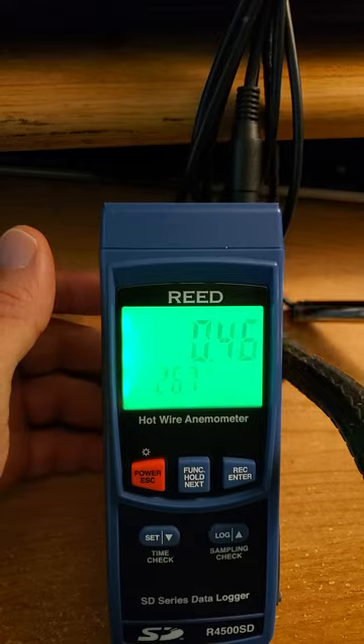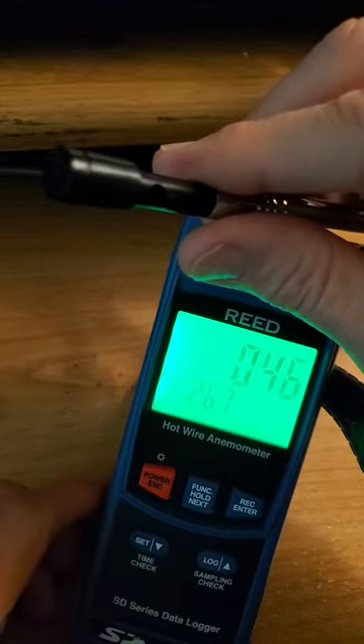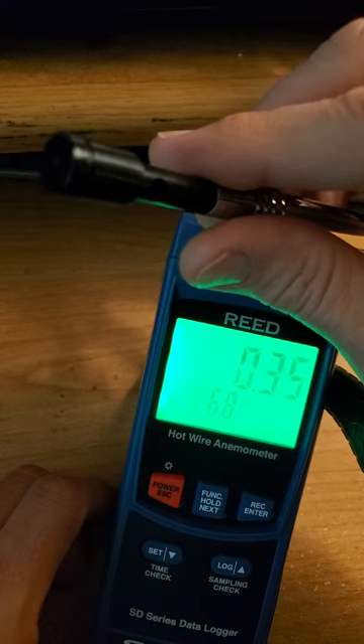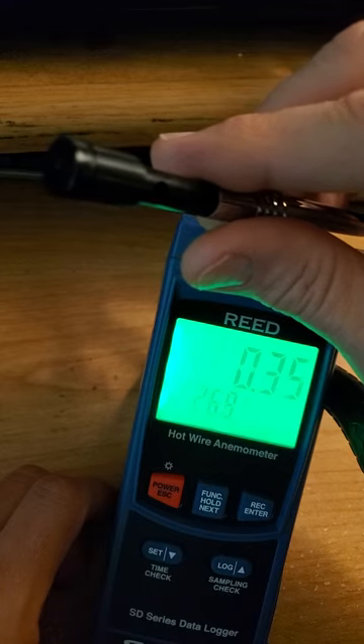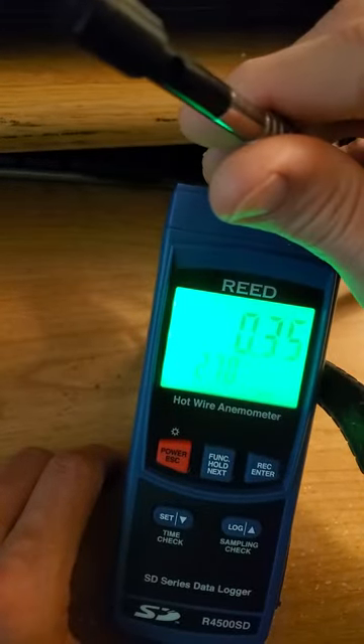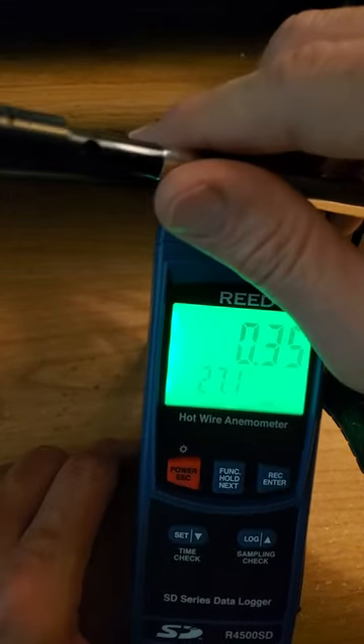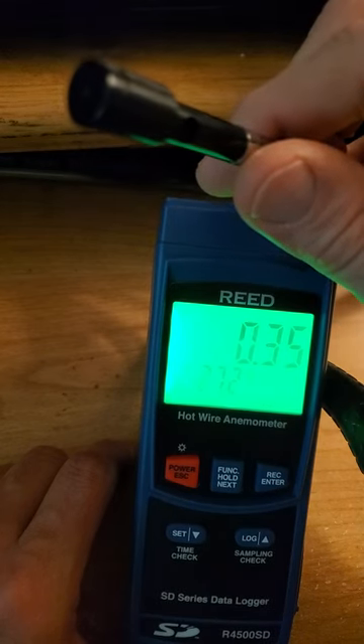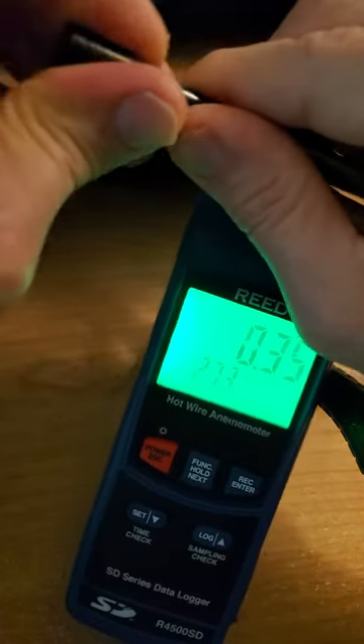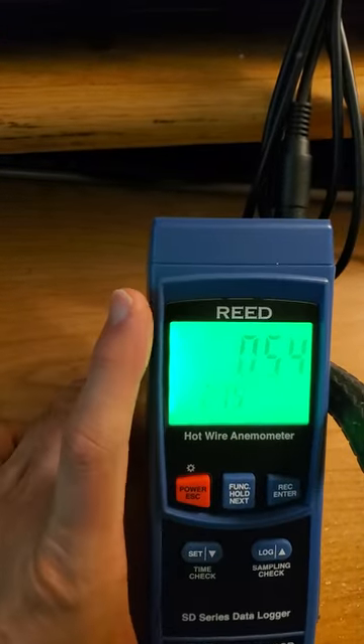There's no wind going through, and I'll demonstrate by closing the probe cover — that even with this closed it does drop, but it doesn't show zero, which makes no sense. This should be sensitive enough to register that the device is closed and thus there's no airflow. Something is miscalibrated, and this is how it was when I first checked it out after I got it — it was around 0.35 closed. When you open it up, then it gets worse. Very, very frustrating right off the bat.